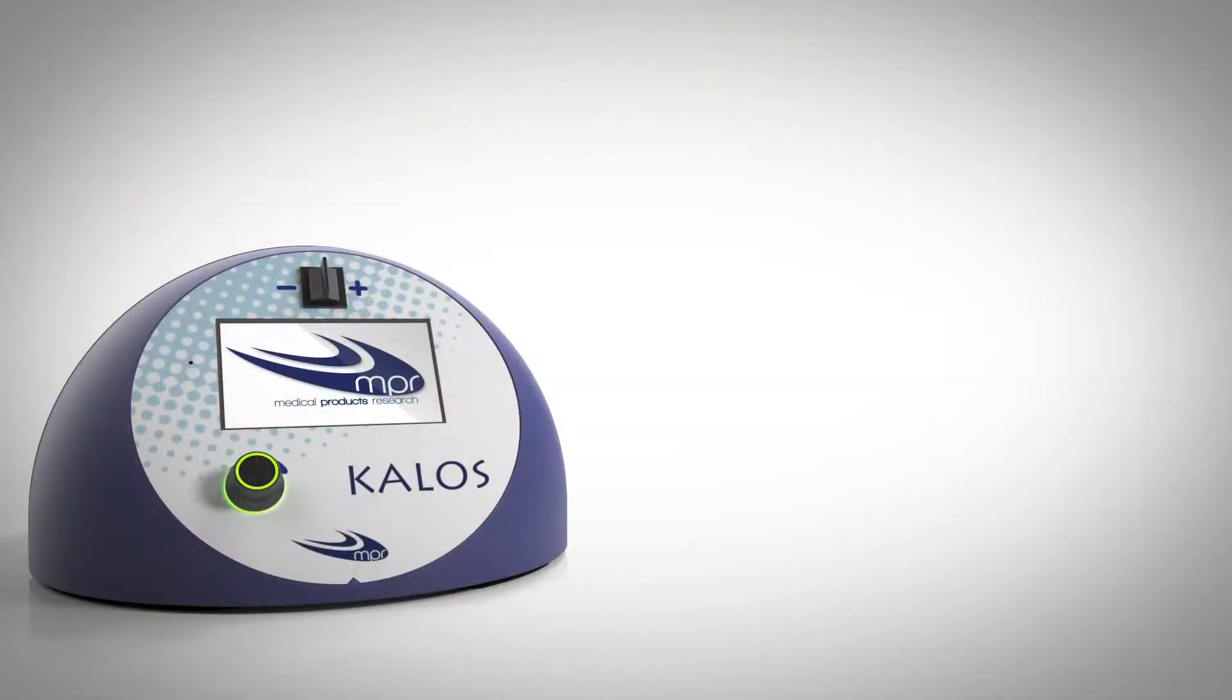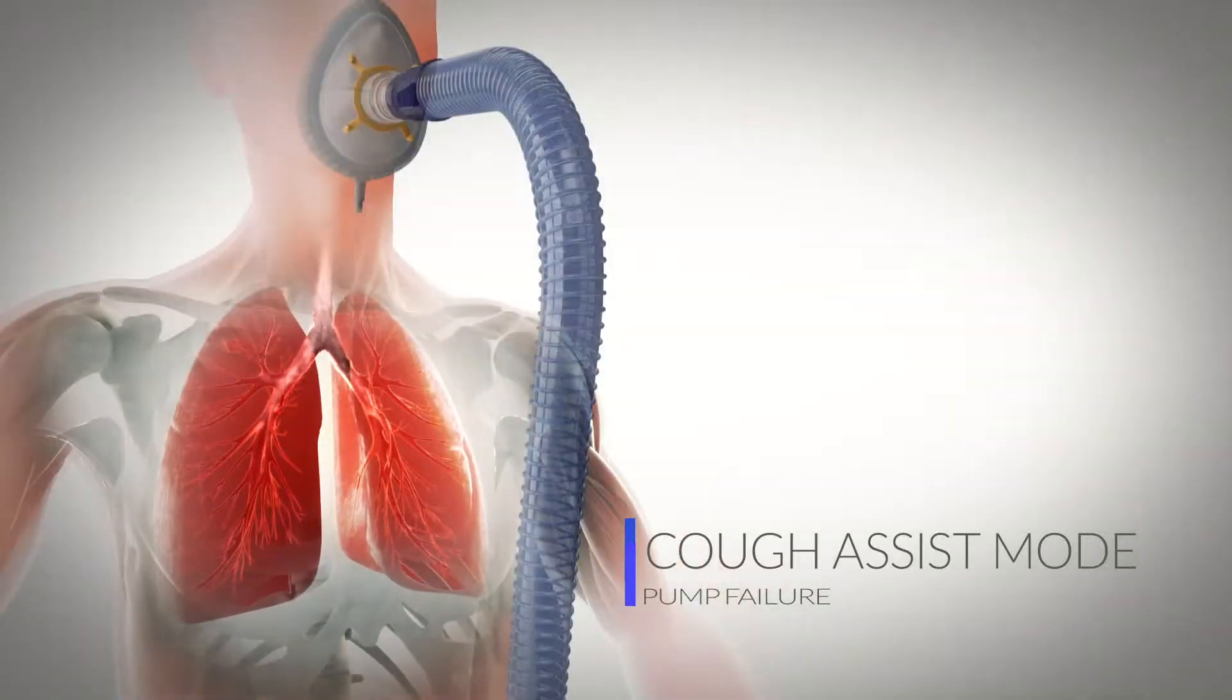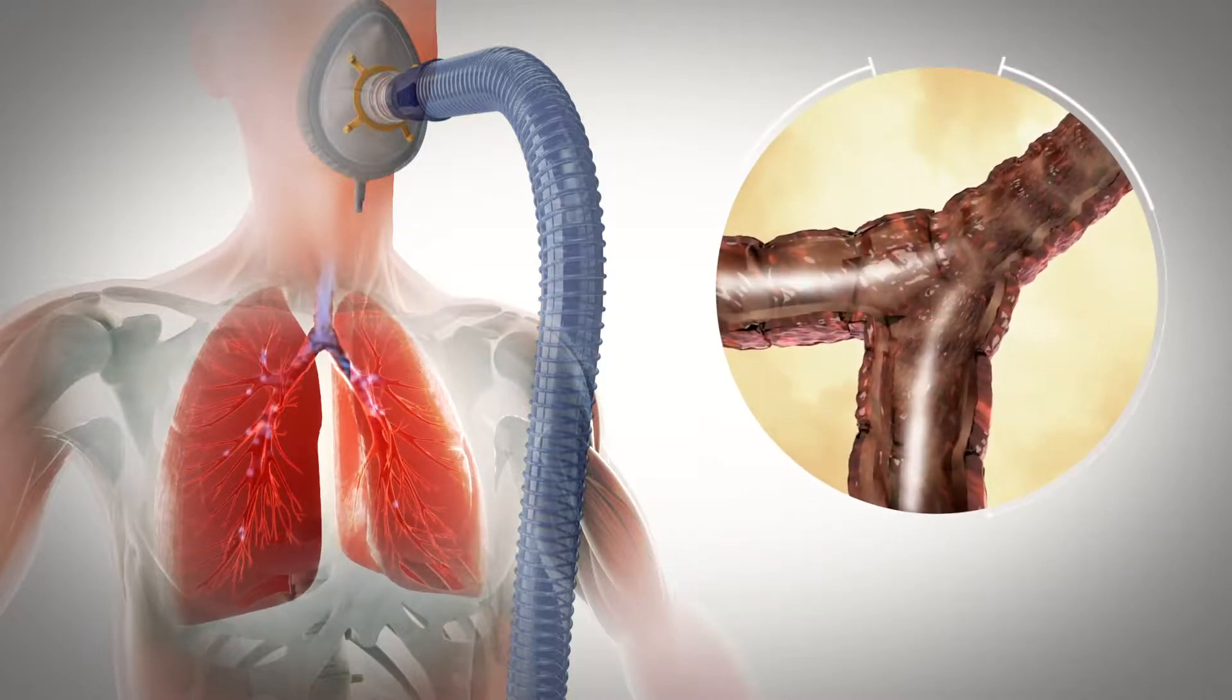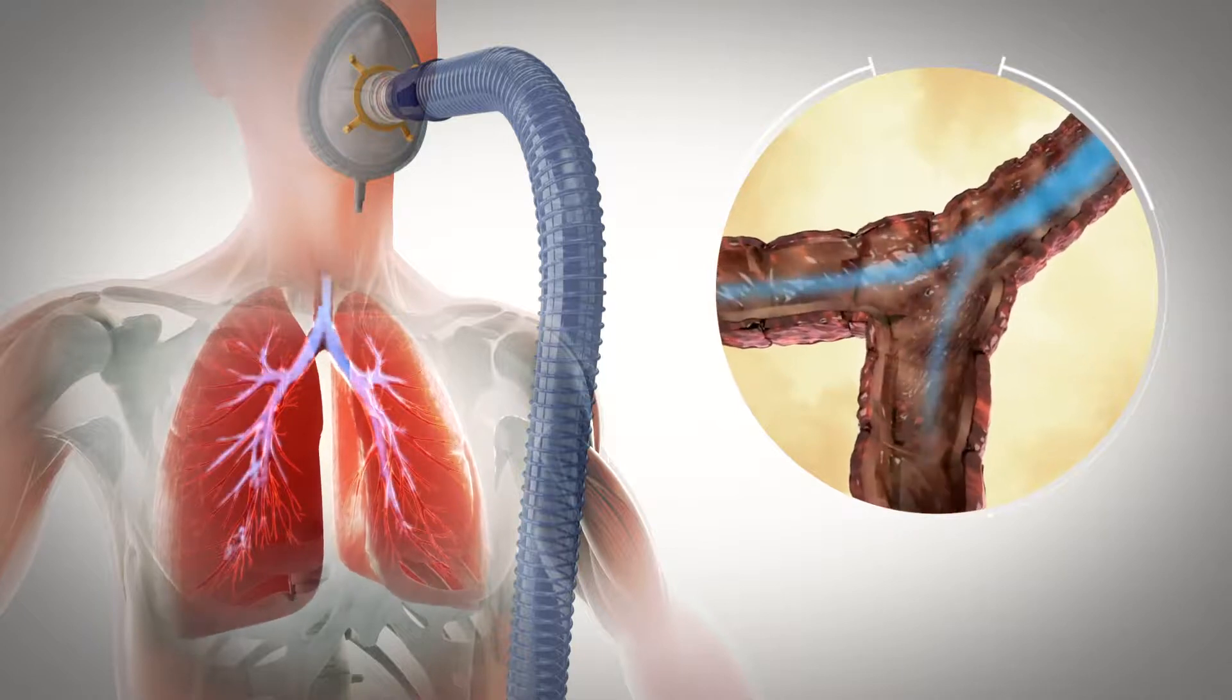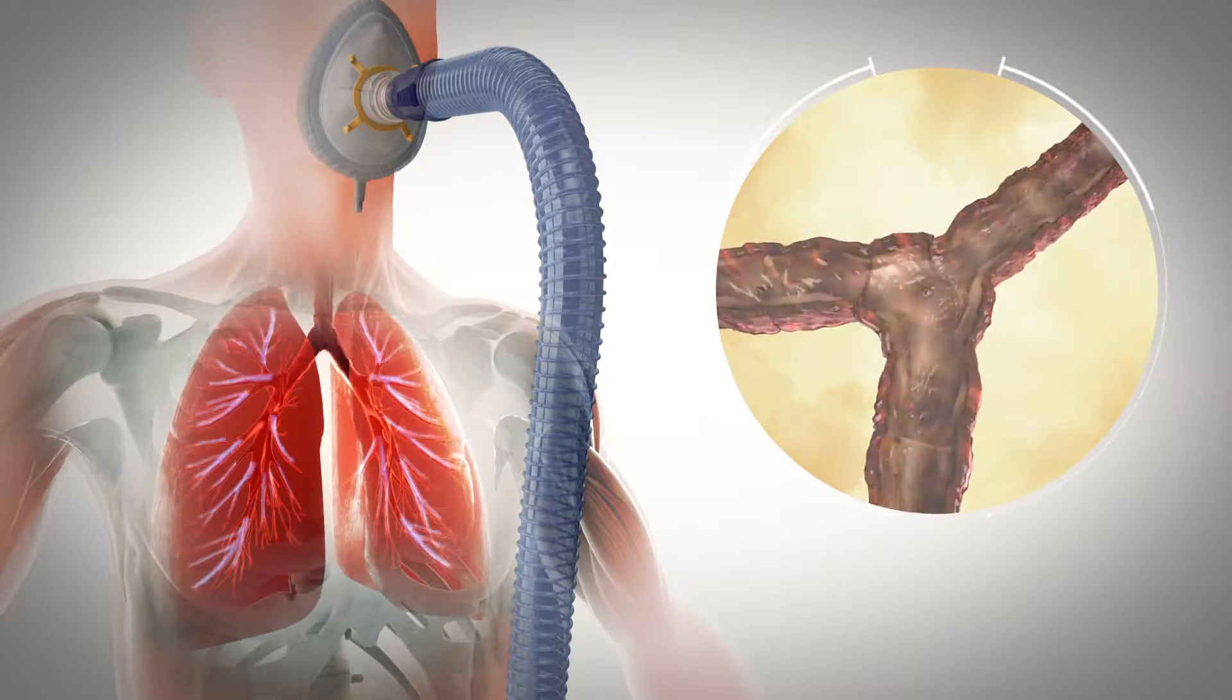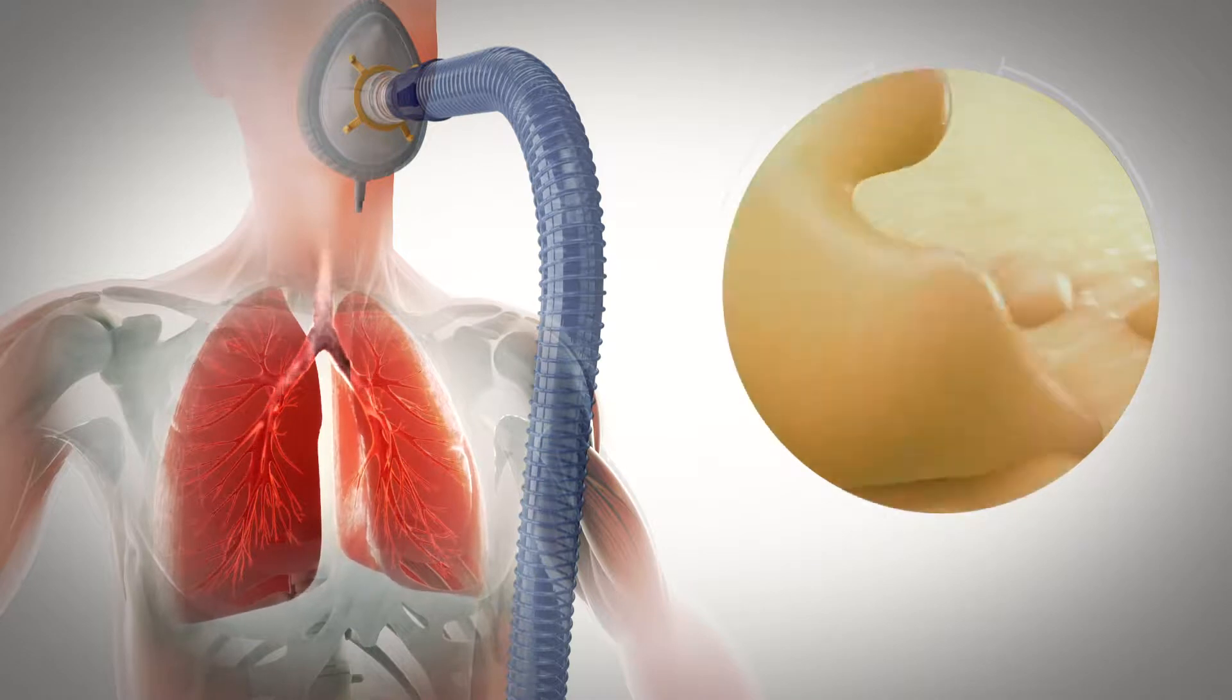Kalos integrates different technologies that support the physiological mechanisms of airway clearance when these are compromised. The cough assist function acts as a substitute in the case of ineffective cough, to clear the central airways from occlusions through the application of alternating positive and negative pressure during inhalation and exhalation respectively. The goal is to maximize the peak cough flow in order to promote the expulsion of secretions.